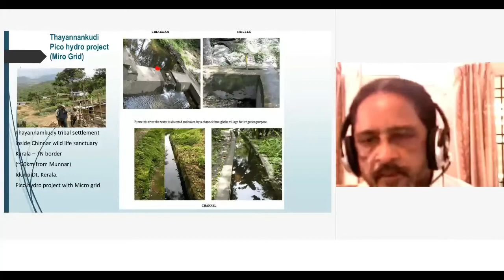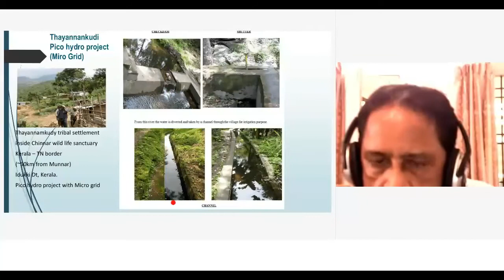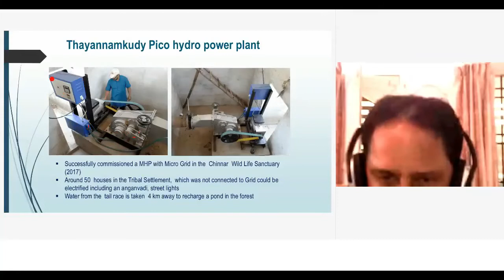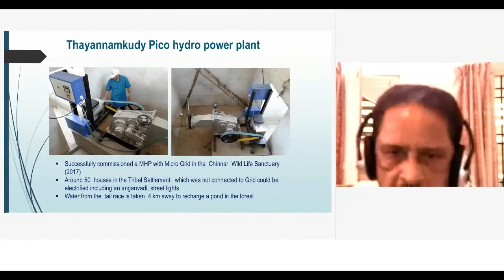The water is taken from the Chinnar River, using an old irrigation channel for this project, with a small weir for diverting water and a channel carrying water to the powerhouse. Since this is a very low head project, we even constructed an underground powerhouse below ground level. You can see the crossflow turbine here, locally manufactured from Coimbatore, along with the generator and controls. And here is August, inspecting that turbine.